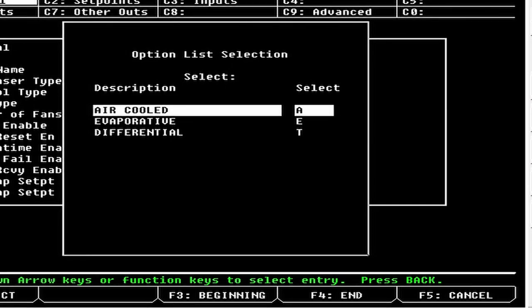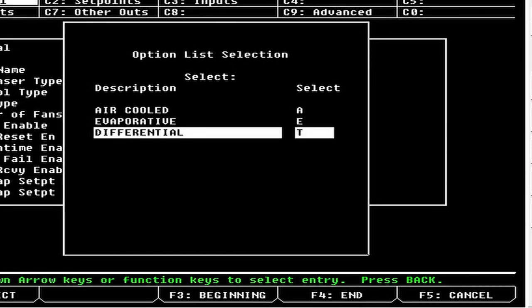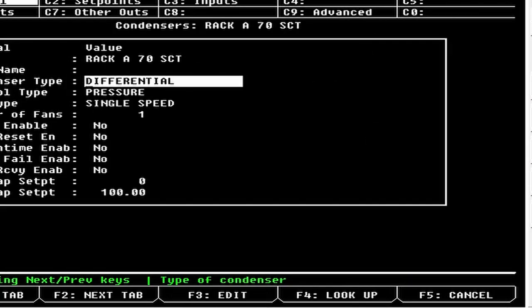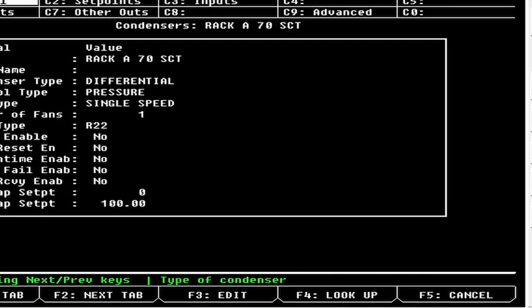Differential is going to be our floating head pressure condenser setup. You shouldn't be using anything besides differential unless you have a cooling tower. If you have a standard air cooled condenser, you should be using differential — floating head pressure saves a ton of money.